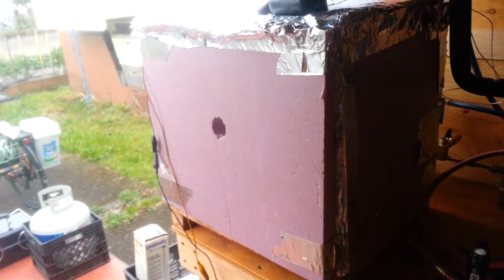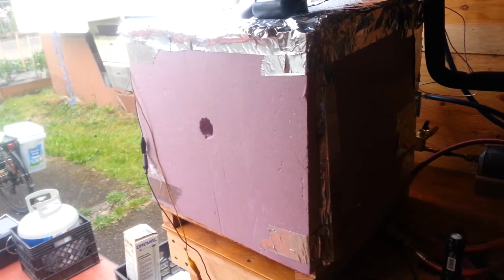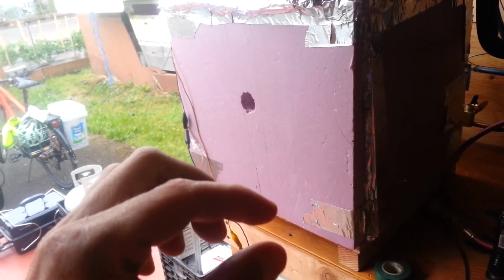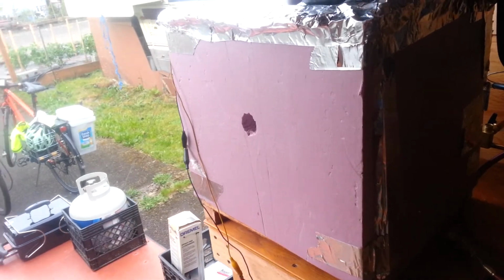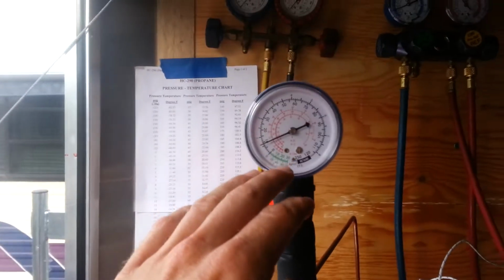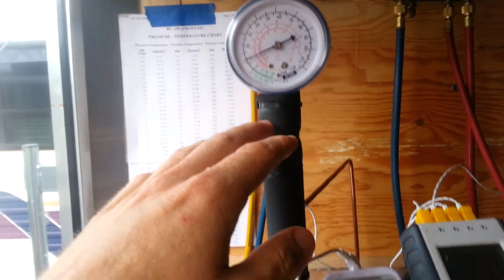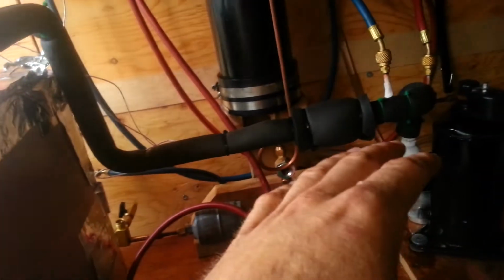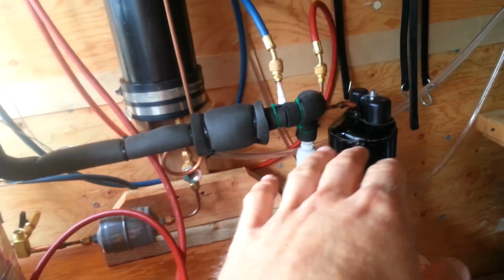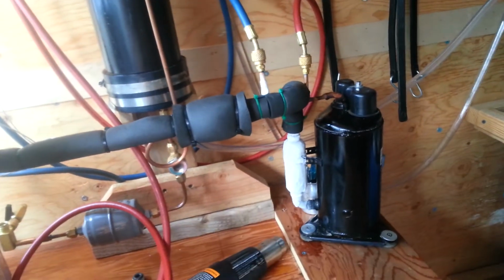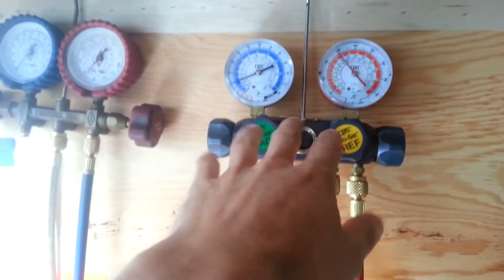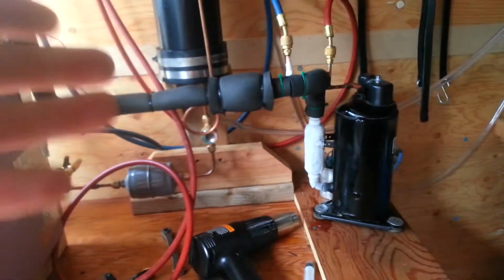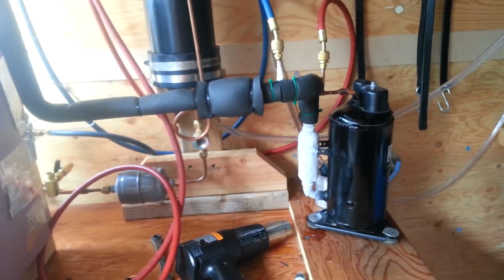Ideally, the way that I see it is that if you wanted the most efficient operation and you wanted to cool something down as efficiently as possible, you want the smallest delta T. The reason being, you want the evaporator pressure to be as high as possible in order to admit the highest suction pressure to the compressor, so it's less work that it has to do. A smaller compression ratio, for instance, and a more dense gas vapor being pulled back to the compressor.